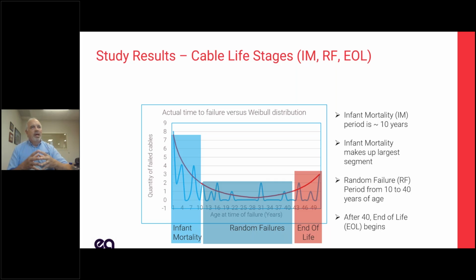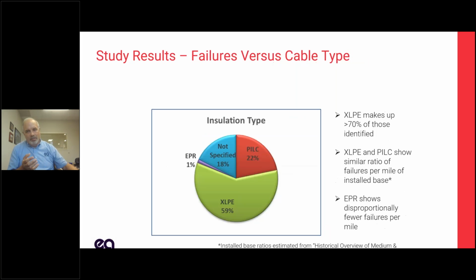So testing that and seeing something's going on, or doing a forensic investigation and finding out that your cable's got impurities in it, it's 40 years old, and it's got water trees, it's got electrical trees, then you know you need to do something. Random failures, it's hard to predict what that is, but the infant mortality, things where I install this and 5 years later it fails. Infant mortality in cables tends to be about a 10-year period, as opposed to electronics where it's a 10-hour period. So you've got this time, you really want to reduce those, and that's where you get down into the workmanship and the testing and commissioning. You do all that right, then your infant mortality is going to go down.